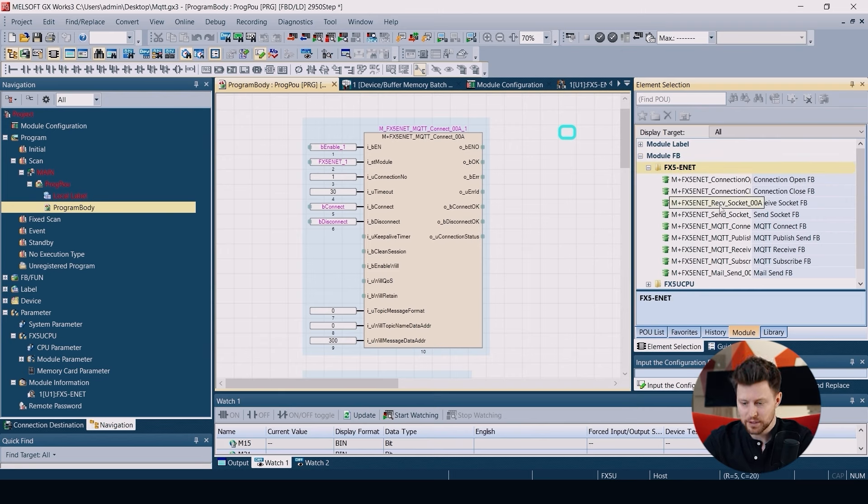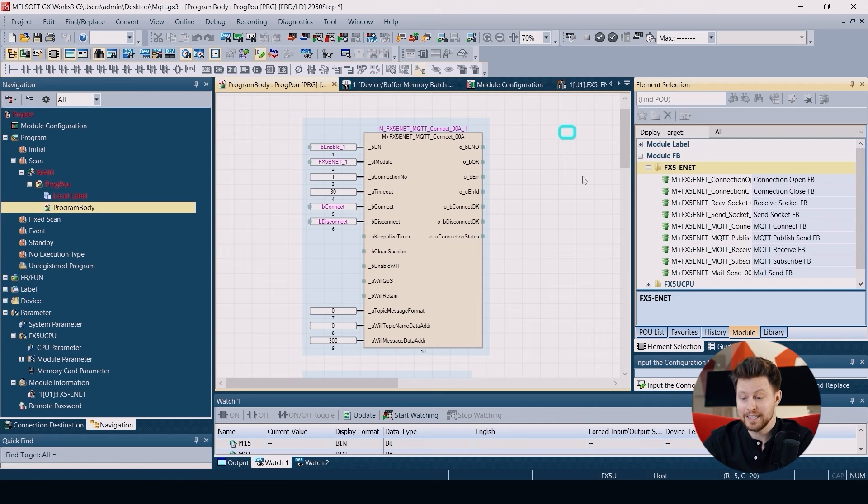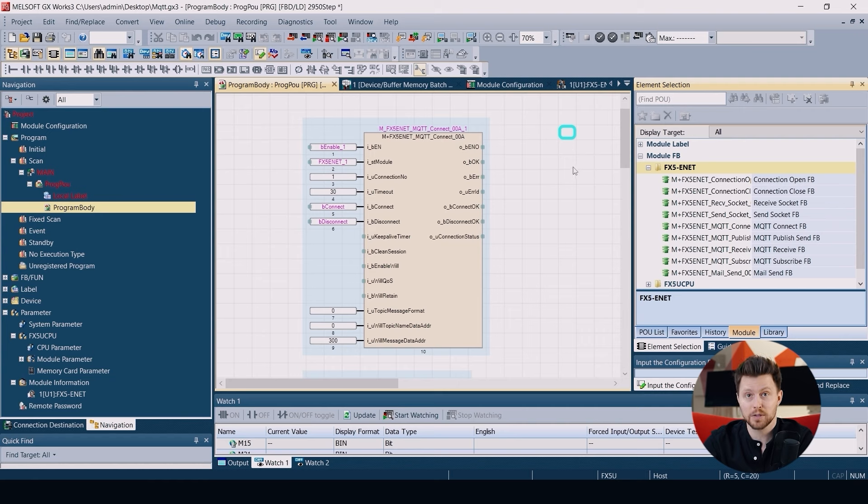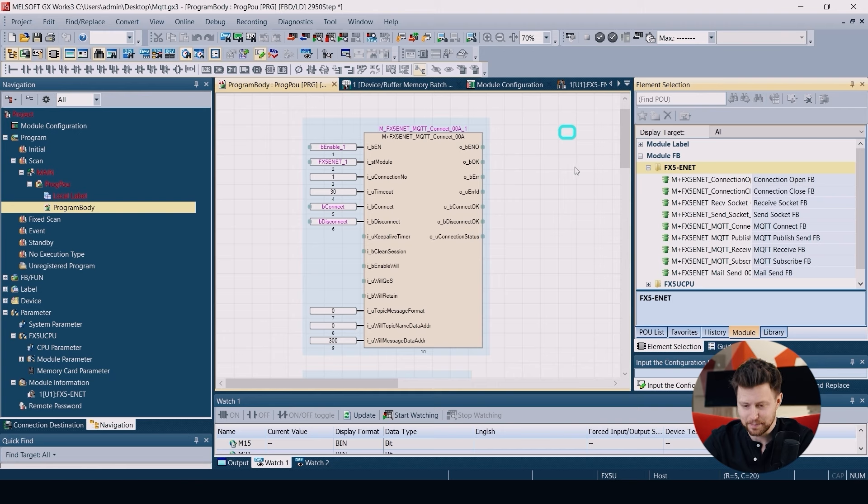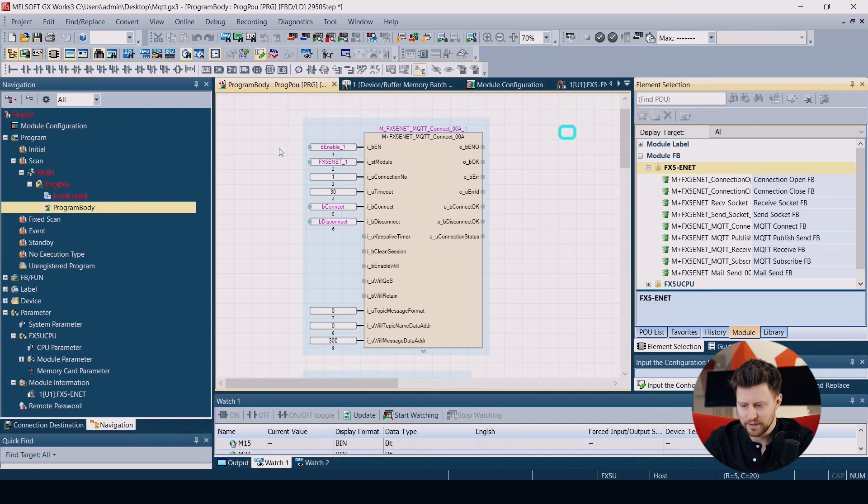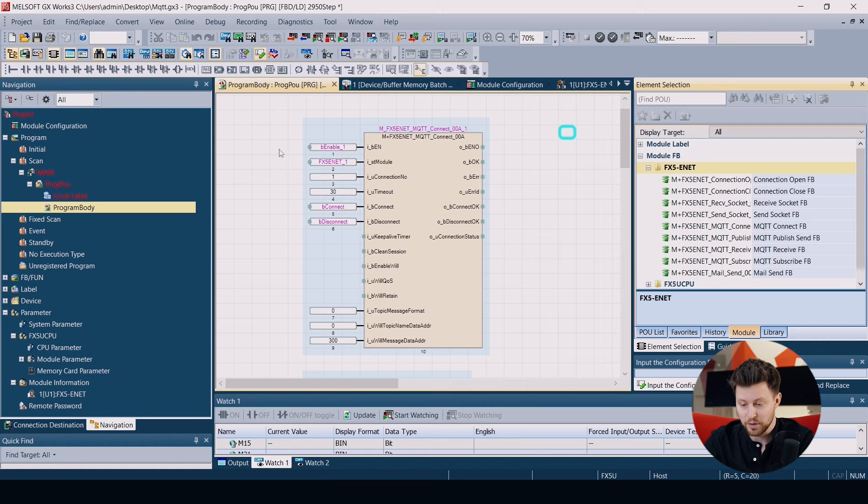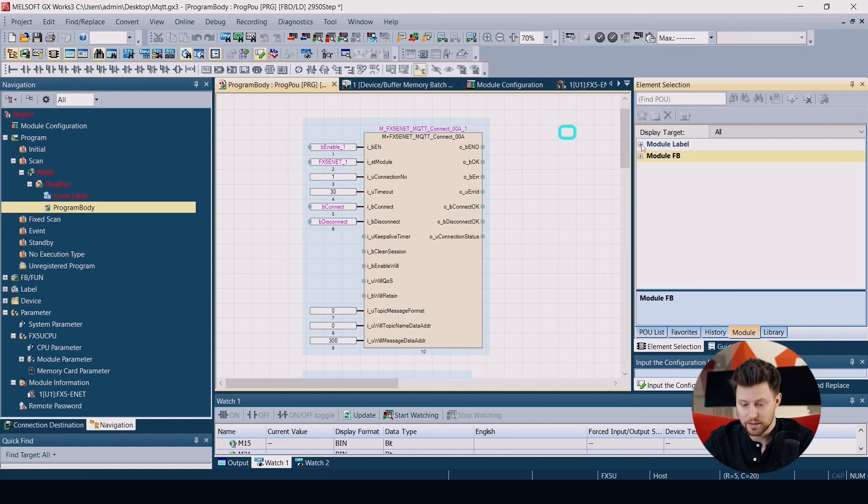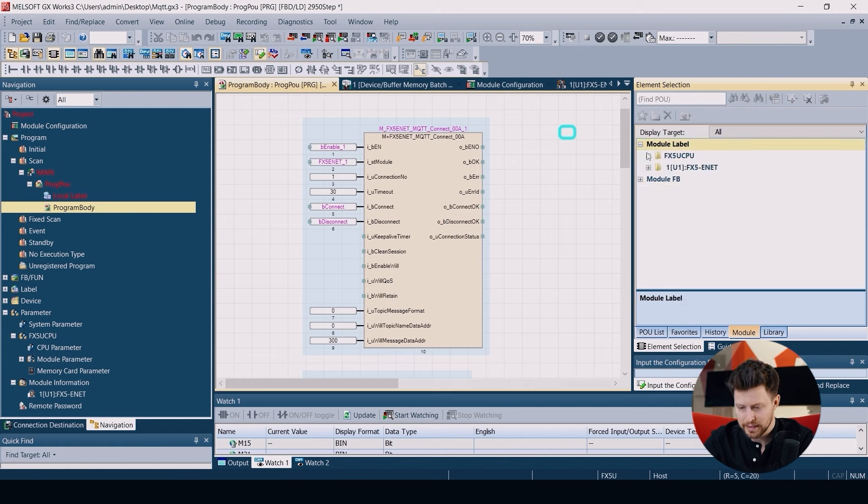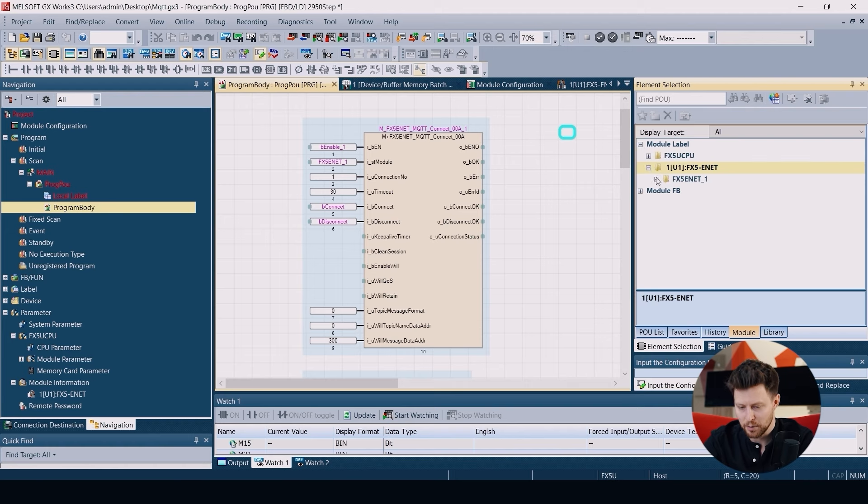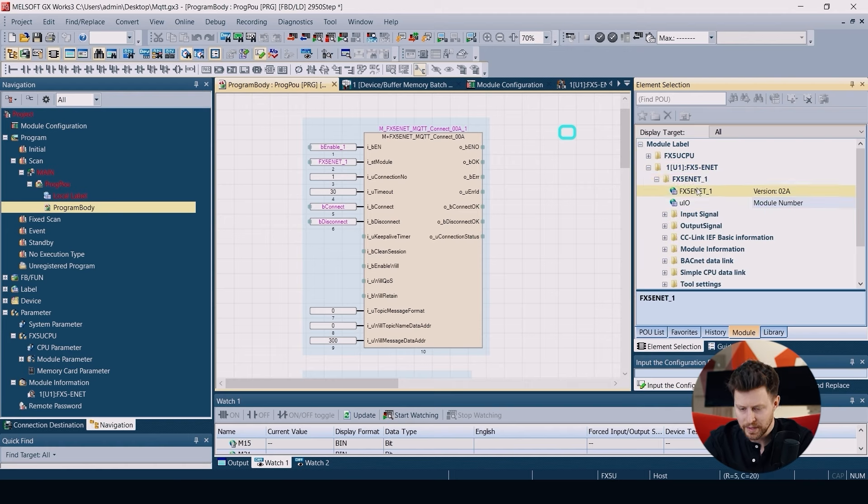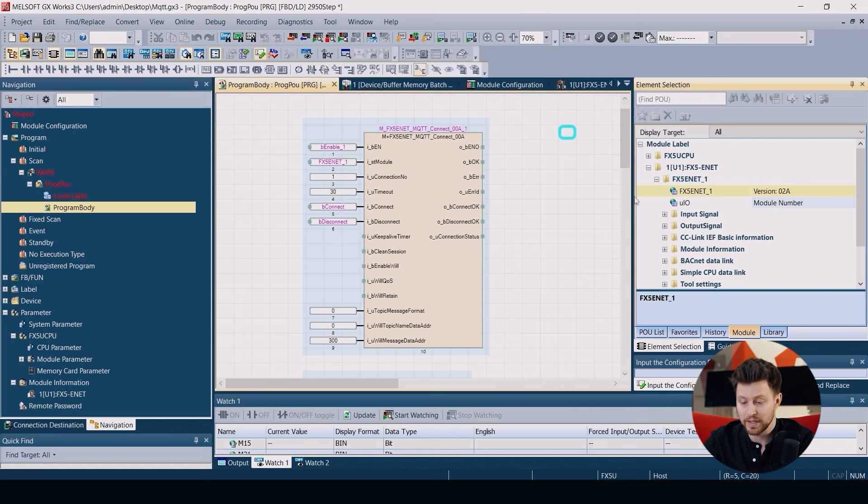The first function block is FX5-ENET MQTT Connect. This block is used to establish the connection itself. First at the top we have the enable input to activate the function block. Then we need to add the structure of our module label that we can find here in the module label FX5-ENET. Here we have our label.